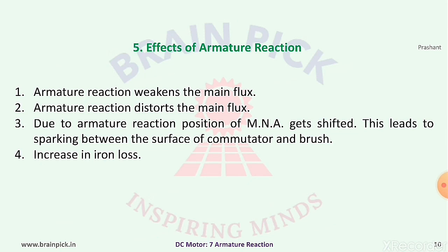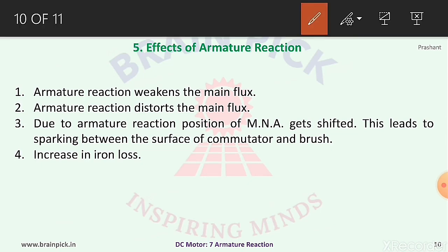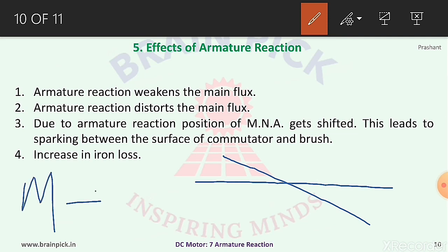The third effect: due to armature reaction, the position of the magnetic neutral axis gets shifted, and this leads to sparking between the surface of the commutator and brush. The MNA shifts from its main position. In a motor, the MNA shifts in the opposite direction to rotation; in a generator, it shifts in the direction of rotation. The fourth effect: armature reaction increases iron loss in the DC machine.